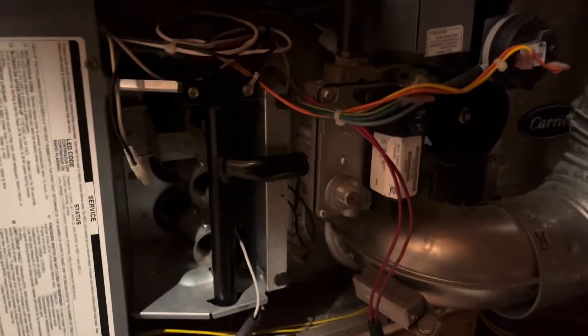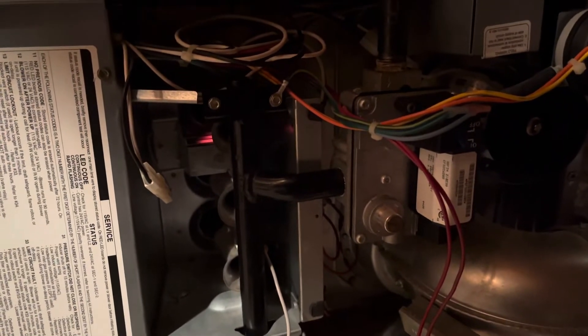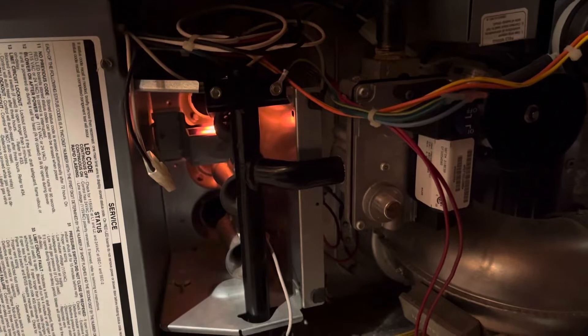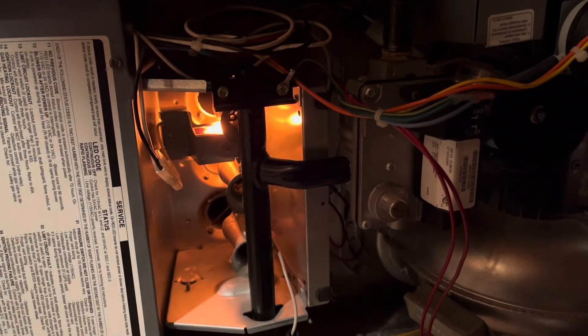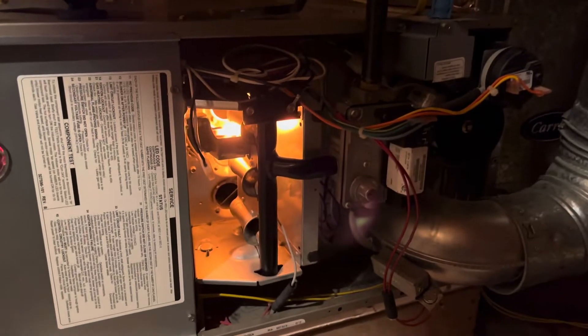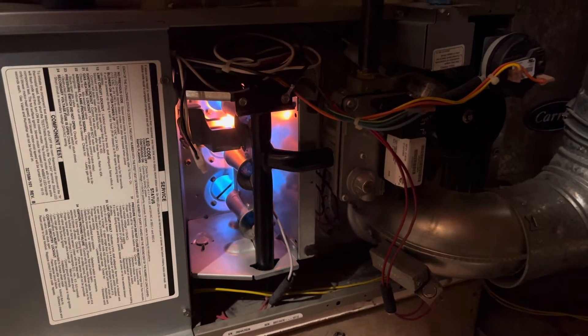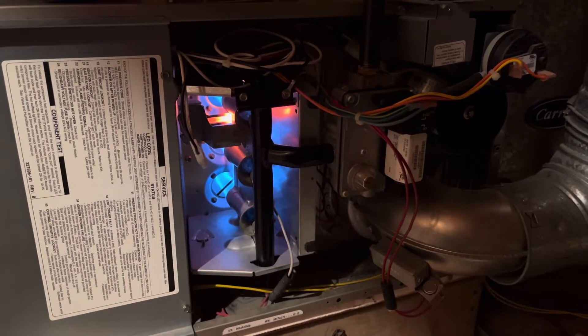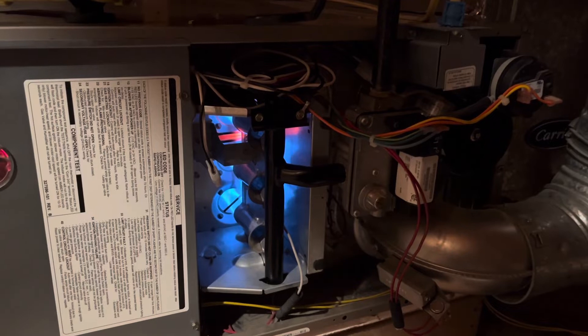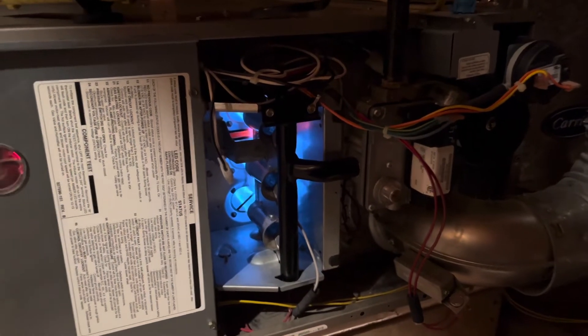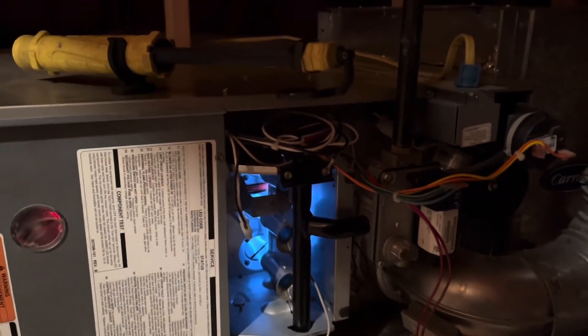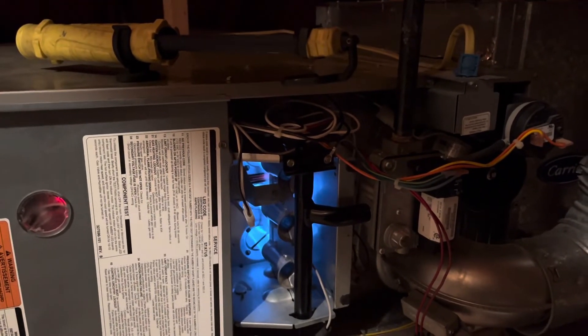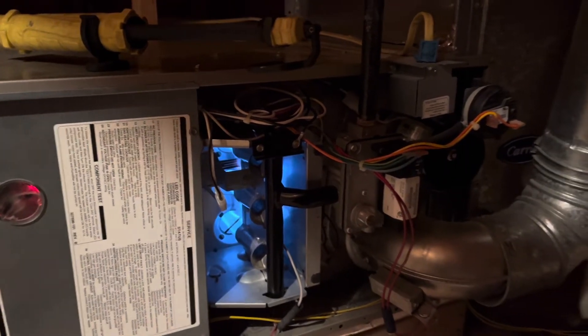Hopefully that was the problem. Yeah, buddy. So if it stays on generally longer than seven seconds, that's usually the issue. But I'm going to run this and make sure my temperature rise is good. And we'll go from there. We'll see what it is.